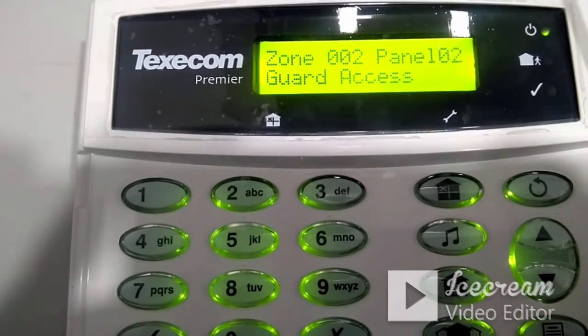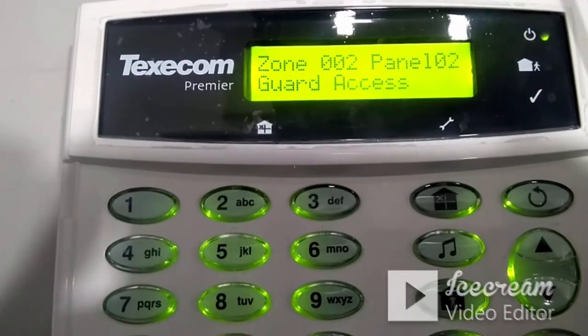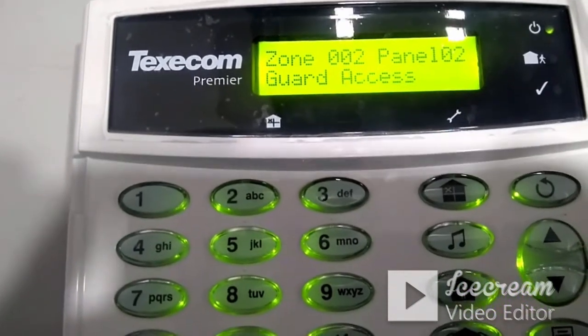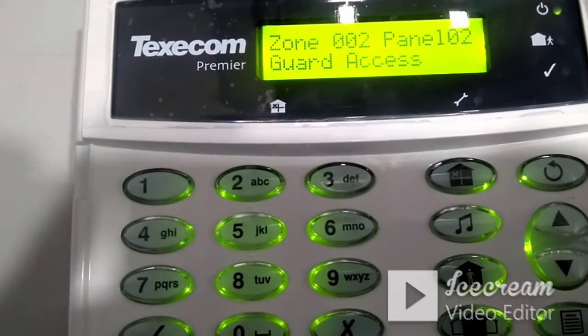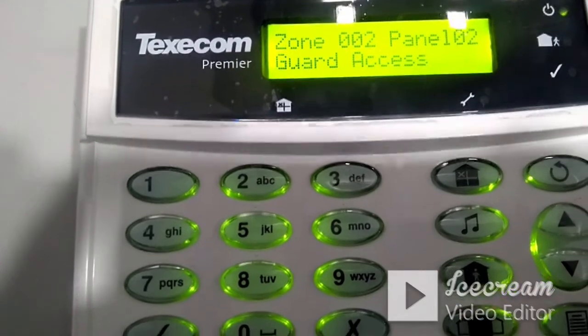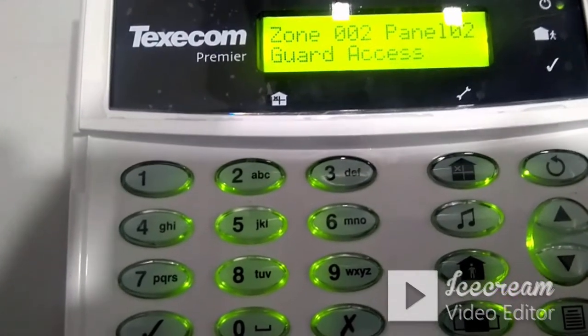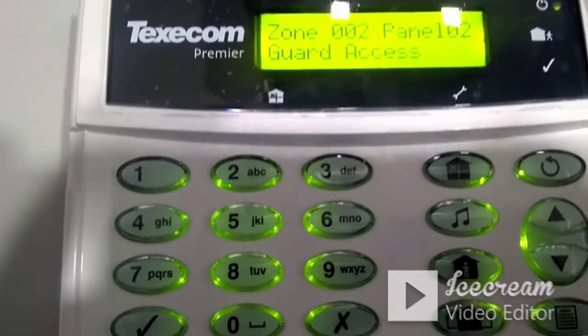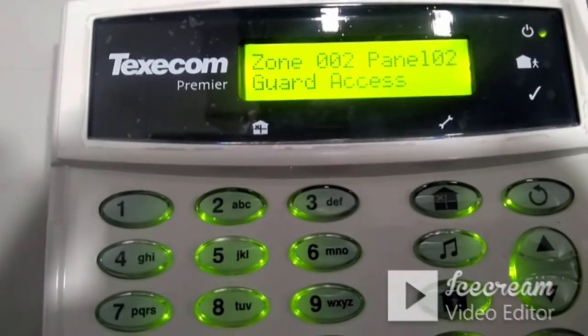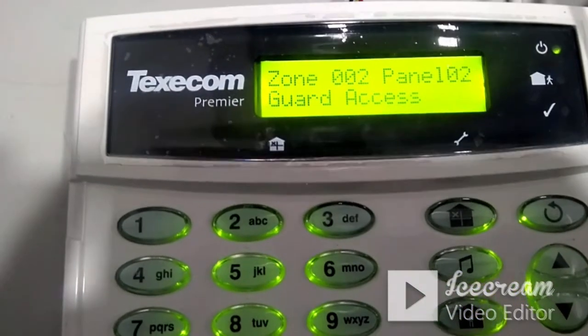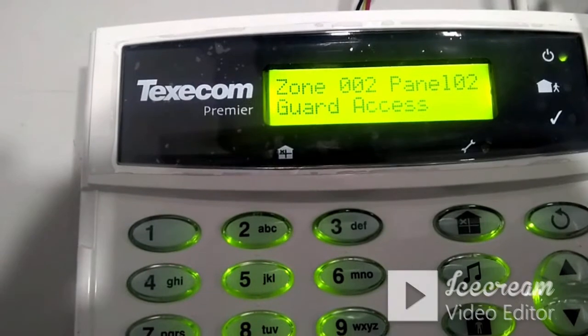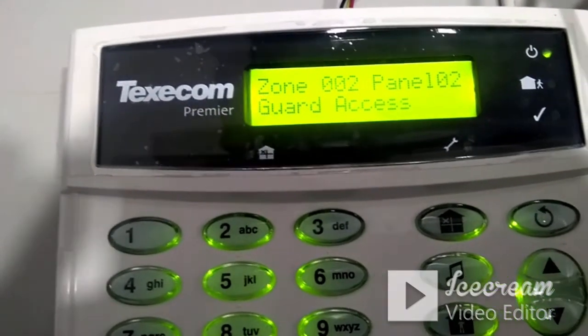If the guard access zone is triggered without the entry/exit zone activating first, the panel will immediately activate the sounder. So a zone programmed as guard access has both entry and exit delay applicable — but the entry delay only applies if the entry/exit zone activates first. If not, the panel will not wait and will immediately trigger the alarm.